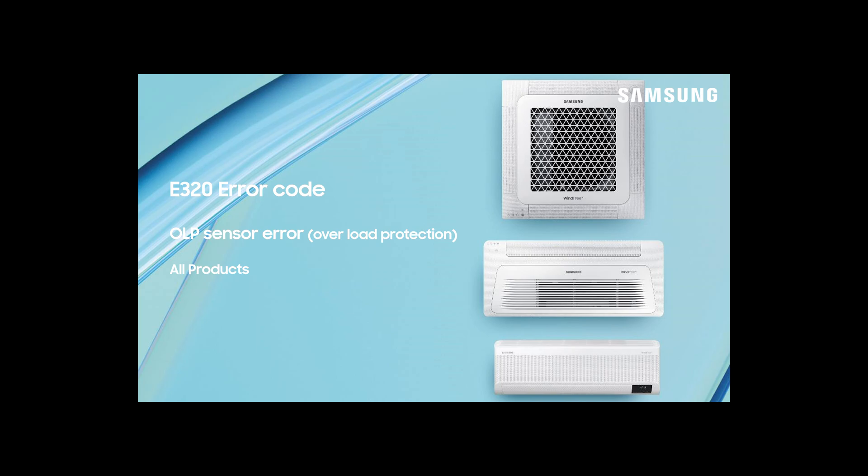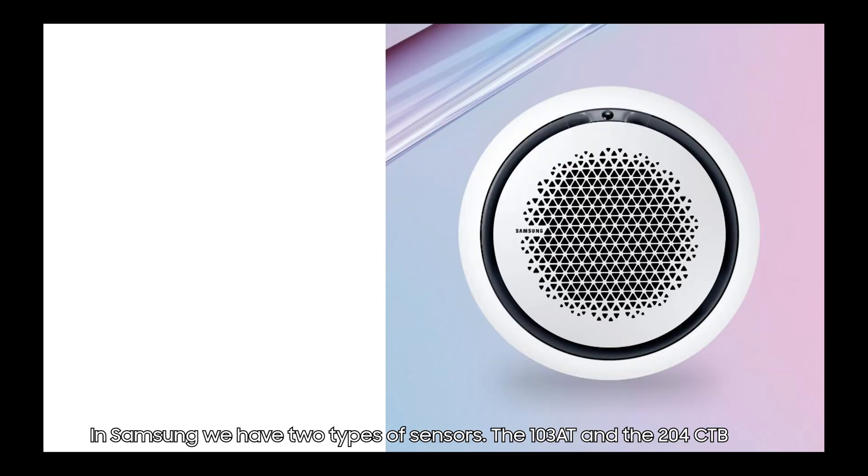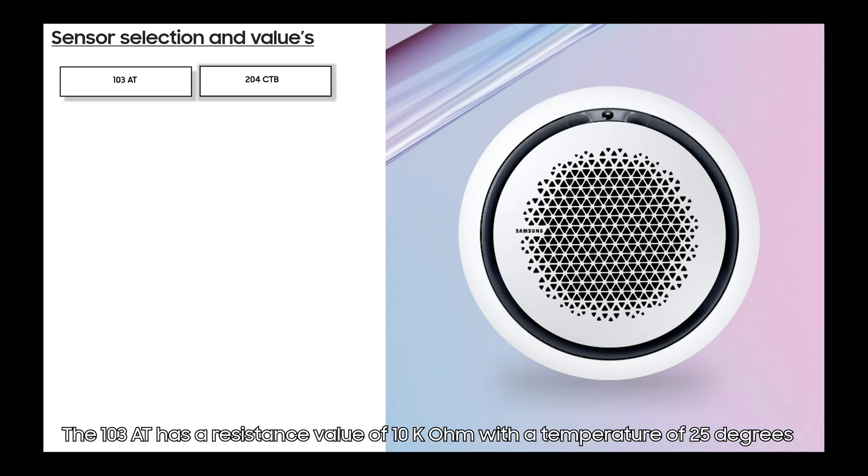First, we will start with some basic explanations about sensors. In Samsung, we have two types of sensors: the NTC 103 AT and the 204 CTB. The 103 AT has a resistance value of 10 kilo-ohms within a temperature of 25 degrees.